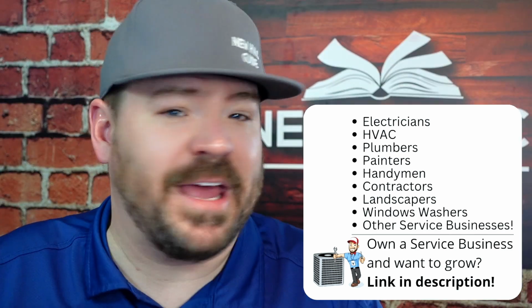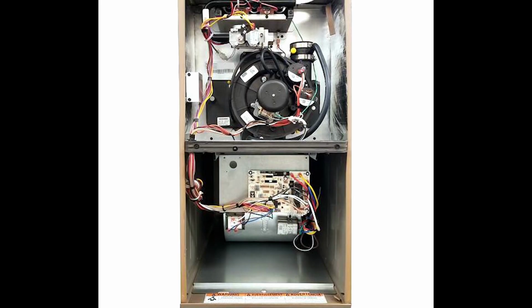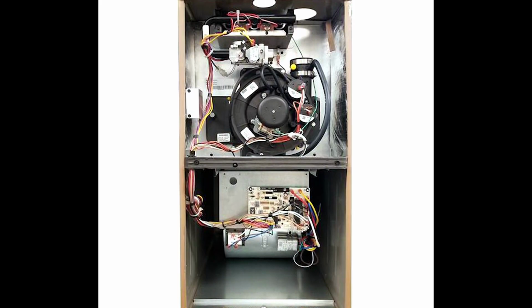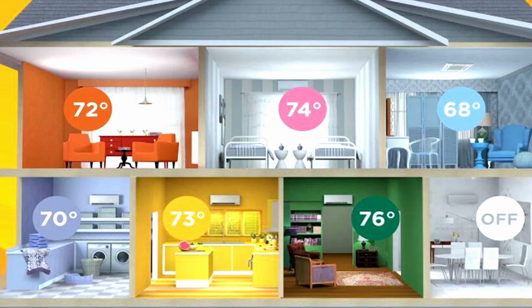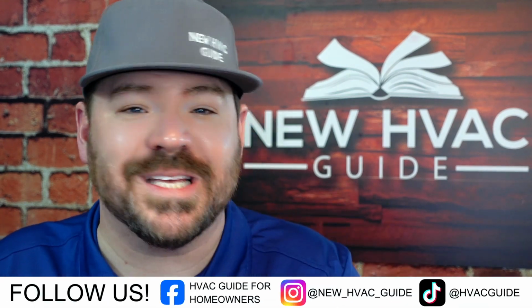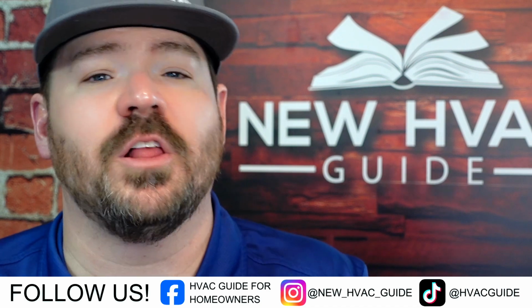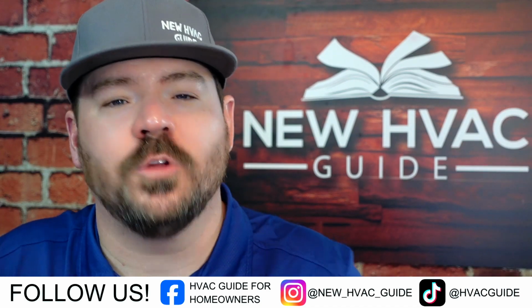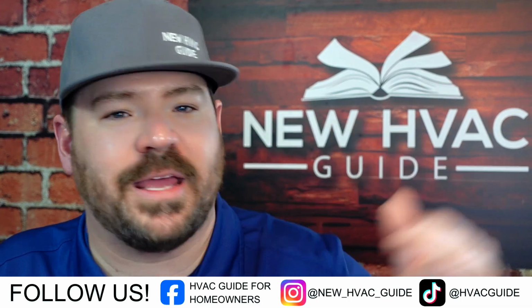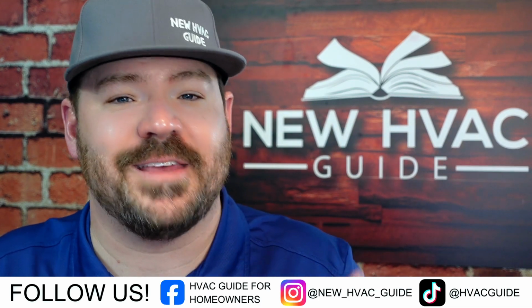Because we've advanced in technology, we used to have old single stage furnaces with big motors that pushed all kinds of air through — we didn't care how much energy it used, just pushing a lot of air through a small hole. But because we've got newer inverter type systems, and zoning systems that can be quite complicated in themselves, there are guys who almost specialize in this now. They really know what they're doing — they can dial in a duct system, maximizing not only comfort and efficiency but even noise. If guys who really know what they're doing install a ductwork system where the HVAC system is ultimately optimized, you could take a good system and make it a great system just because of the Manual D and the installation of the ductwork.